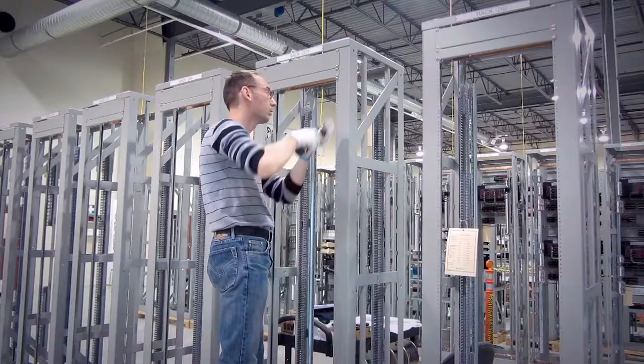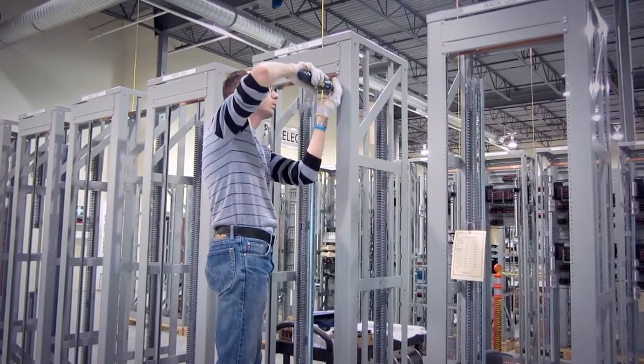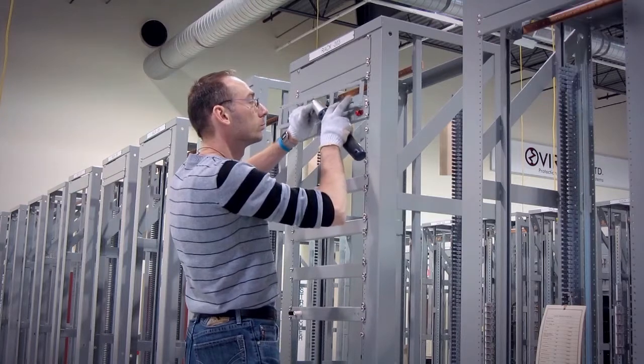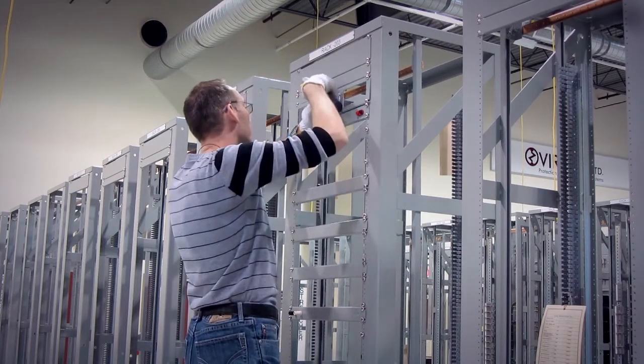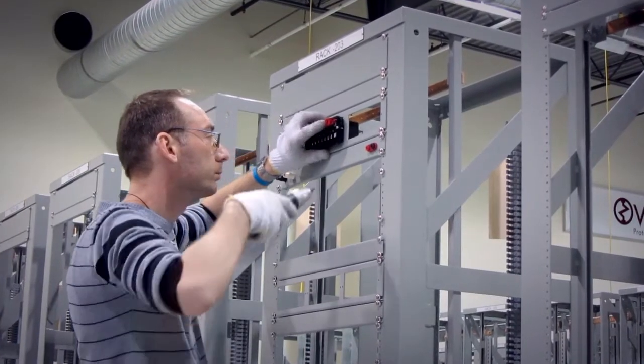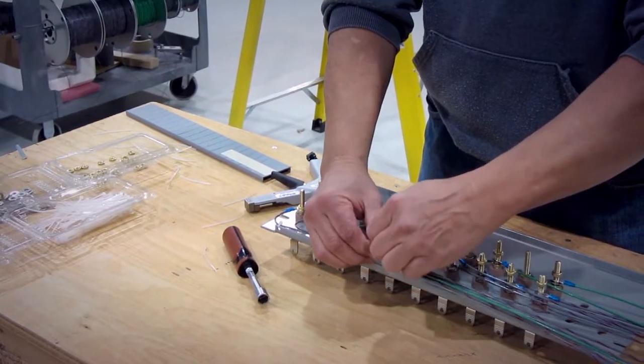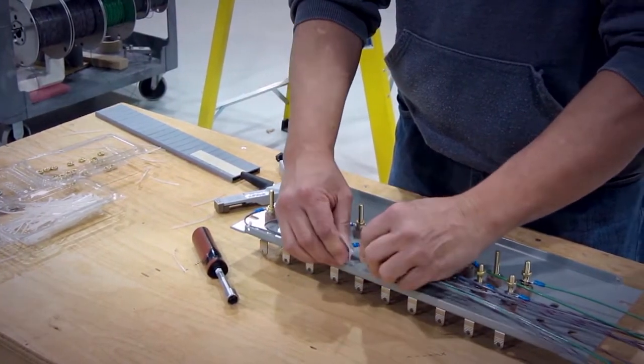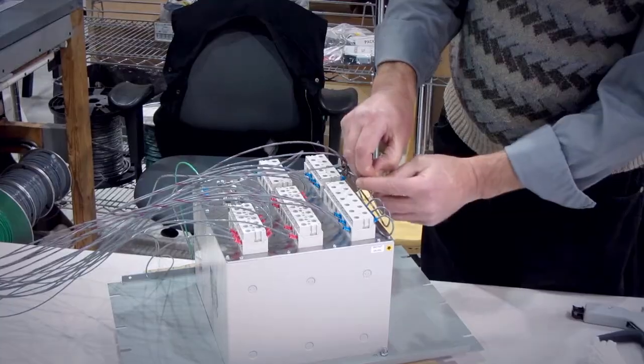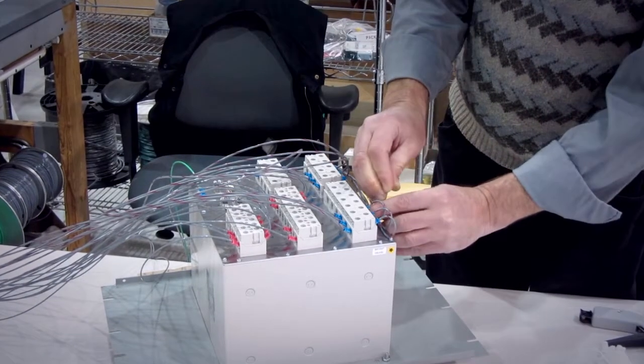Common items such as terminal block mounting rails, wire ducting, and ground bars are installed. Then front panel racking components and mounting plates are assembled on the panel mounting rails. Depending on the work, some subsystems are pre-assembled on the workbench and wired prior to installation in the control panel.